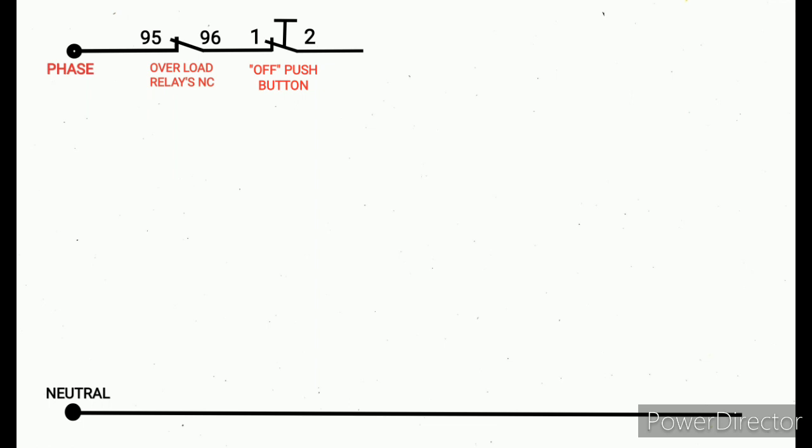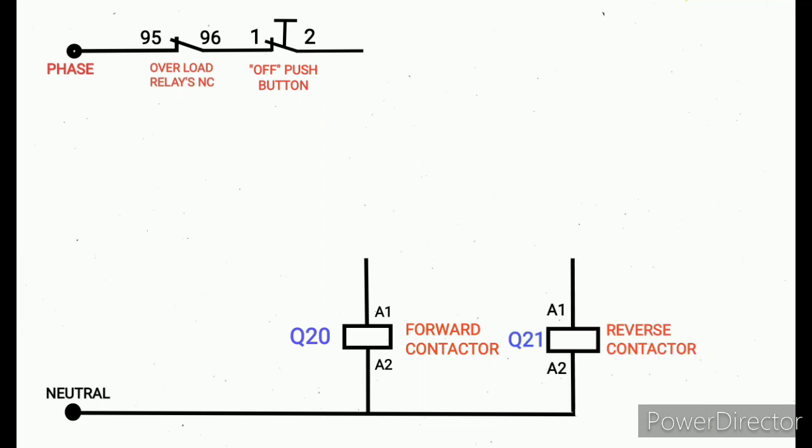Next we are going to draw both contactors, forward and reverse, with interlock. First we're going to draw forward contactor. I named here Q20. A2 is connected to neutral, the A1 will be connected later. Next we're going to draw reverse contactor, I named here Q21. This is similar to Q20, A2 is connected to neutral. Next we have started to draw interlock. This is the interlock logic.